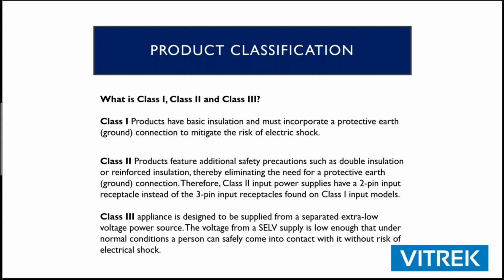So the other very common category you guys are familiar with, I'm sure, would be a class 2. That's something that's double insulated. It's going to have a two conductor power cord, just line and neutral, 2 blades. These are going to be blow dryers, blenders, things like that. Pretty much anything that's handheld is going to fall in the class 2 category. A lot of plastics are used these days, a lot of overmolding, things like that.